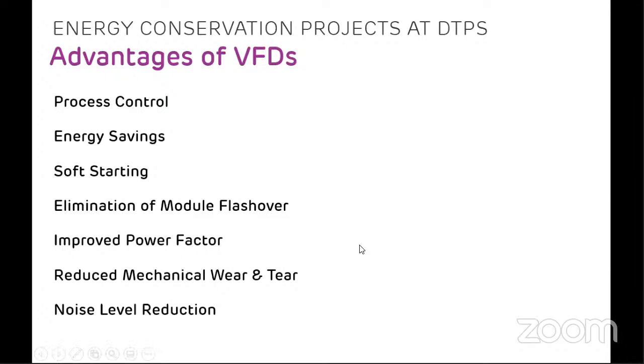Power factor is a key parameter in electrical power consumption. Generally, induction motors which are lightly loaded have a very poor power factor. Therefore, their energy consumption is higher. So if you use variable frequency drives, it brings the power factor near to unity. Power factor is from 0 to 1, and 1 is a very good power factor. Normal induction motors have a power factor near 0.8 or 0.9. So variable frequency drive run motors have a good power factor. Therefore, their energy consumption is lesser.